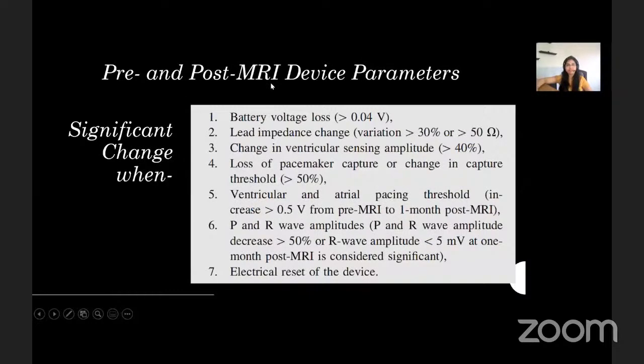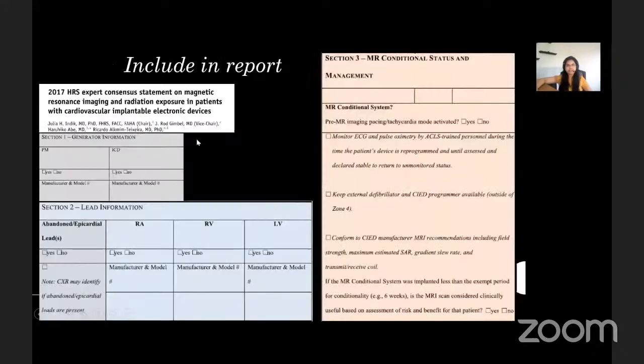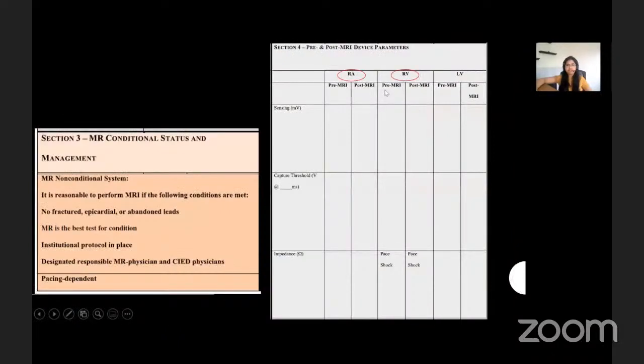Regarding limits of acceptable device parameter change post-MRI: further follow-up or referral to a cardiologist is needed if battery voltage loss is more than 0.04 volts. Remember the 30, 40, and 50 percent rule for significant change in lead impedance, ventricular sensing amplitude, and pacemaker capture threshold respectively. Also record the ventricular and atrial pacing thresholds, changes in the P and R wave amplitudes, and whether there was an electrical reset of the device during the scan. The Heart Rhythm Society paper previously described also has a report template that can be adopted into your practice, serving as a checklist — it requires recording of generator information, lead information, MR conditional status, and has a column for recording pre- and post-MRI device parameters.